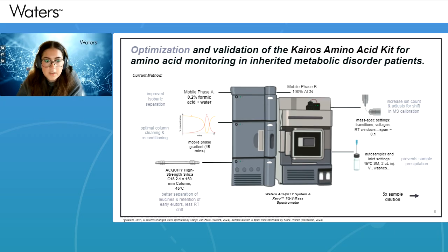We've adjusted some smaller settings as well, including span. So we've increased that to 0.1 for every analyte, just to adjust for any shifts in mass spec calibration. And we originally had our sample manager at 10 degrees Celsius, but we've increased that to 15 degrees Celsius just to prevent sample precipitation. Originally, we also didn't perform a sample dilution, which we now do, a 5 times dilution.